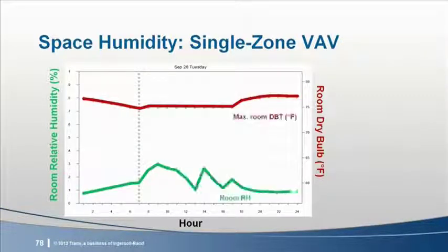With this system, the relative humidity does spike as occupancy begins in the morning, but the peak never reaches the same level of the constant volume system for the same classroom. For this system, the relative humidity remains lower than the constant volume system. The data can be copied and pasted or exported to your favorite spreadsheet tool.